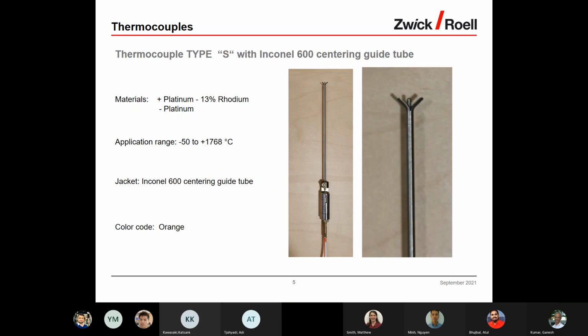Next one, type S with Inconel 600 centering guide tube. The materials are, on the plus side, platinum and 13% rhodium, on the minus side, platinum. Application range is from -50 to +1768 degrees Celsius. The jacket here is the Inconel 600 centering guide tube. The color code is orange.